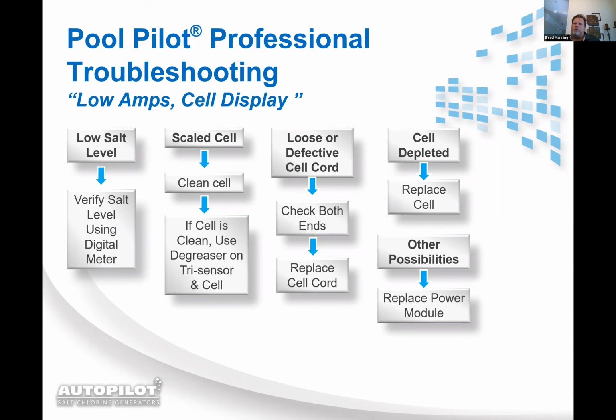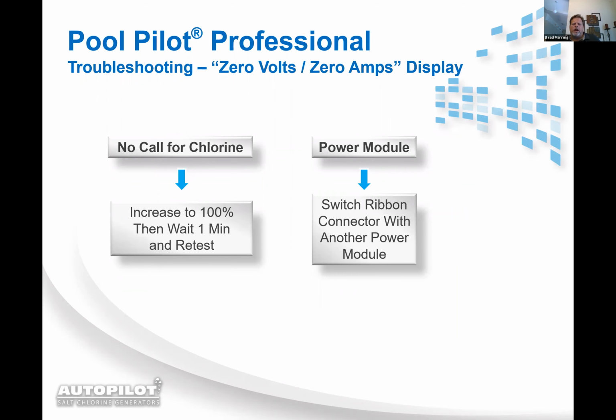Make sure that the cell cord isn't burned up down at the plug that goes onto the cell, or you want to make sure that it's not burned up at the terminal block that it gets hardwired to. And then you want to check the cells for physical depletion. 0 volts, 0 amps, you want to make sure that there's an actual call for chlorine. You know, the Pool Pilot Professional does have a boost mode.